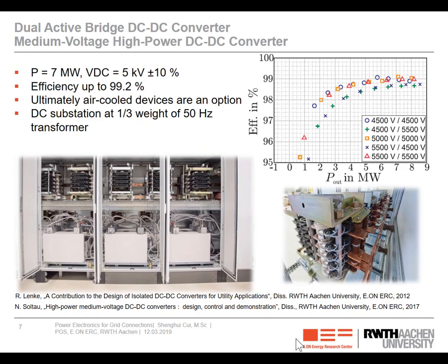And here, this is the converter that we are going to see tonight. It is 7.5 megawatt maximum. We designed and constructed it at our institute. As you can see here, the maximum efficiency at different voltage ratings can be as high as 99.2%. And in the future, ultimately, the converter will be operating so efficiently that we wouldn't need water cooling anymore. So our ultimate target is to make it as efficient as possible, so that we can directly use air cooling to significantly enhance the reliability of the converter.